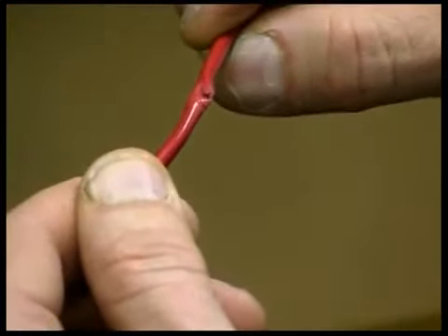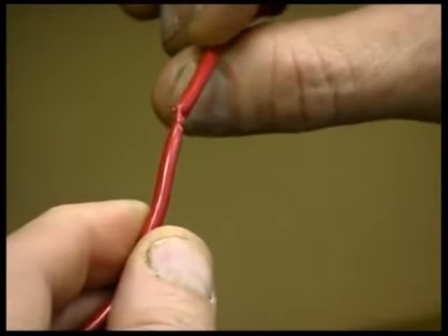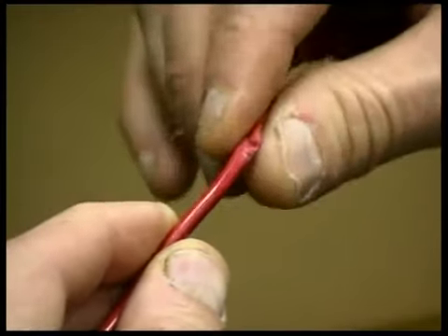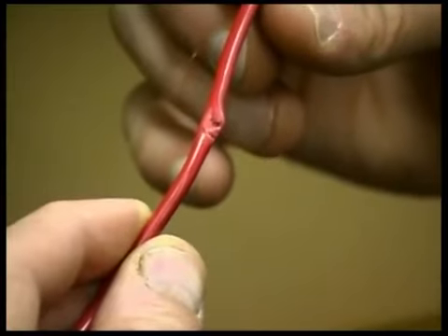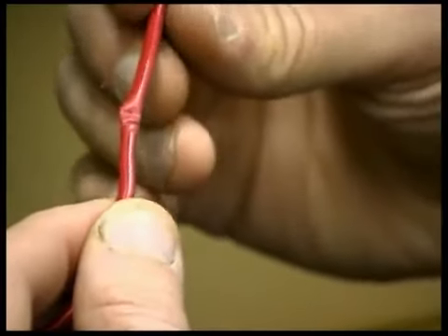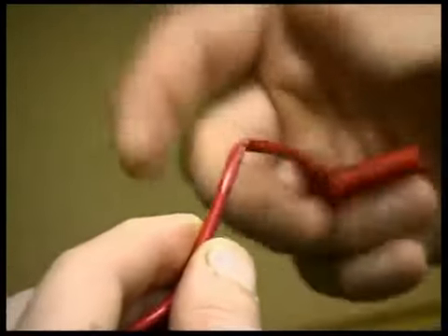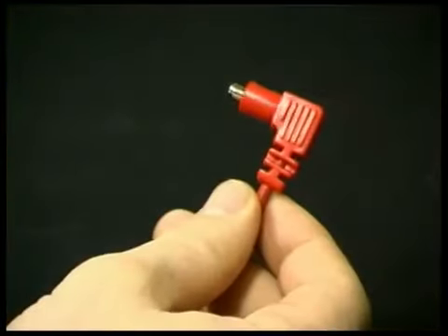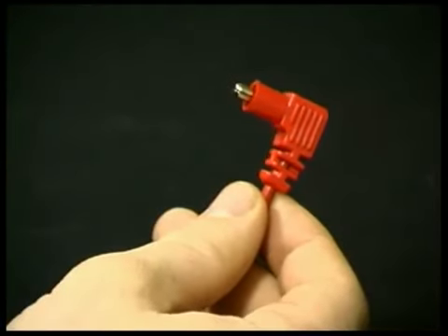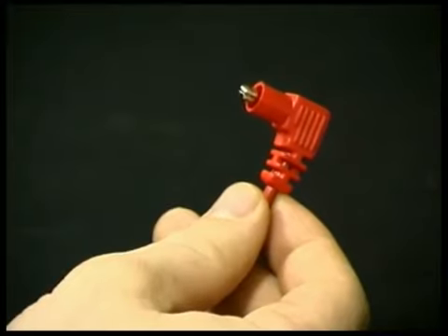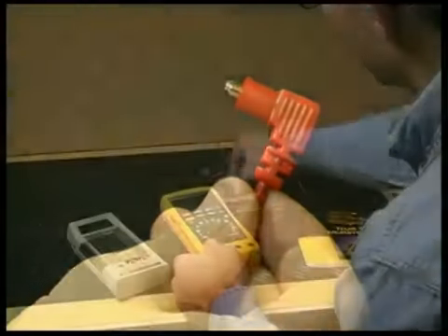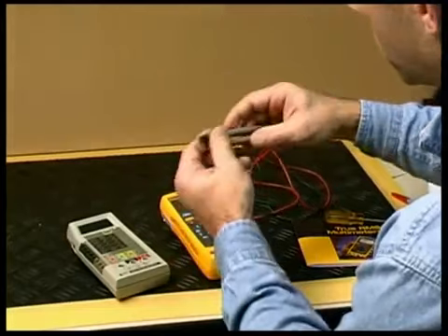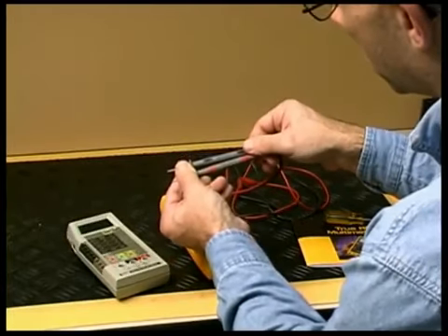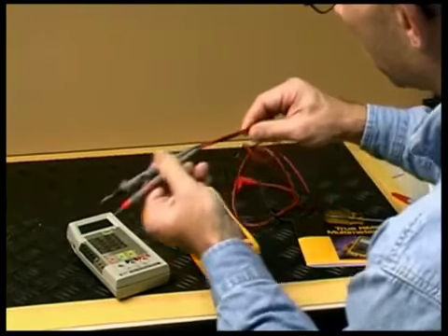Test leads can become frayed. If the probe tip is connected and a damaged or underrated test lead comes in contact with another conductor, a fault may result. The same thing can happen if an unshrouded test lead comes out of the meter and touches a conductor. Always inspect your meter and test probes before using them. Please refer to the guidelines provided at the end of this video on what to look for.